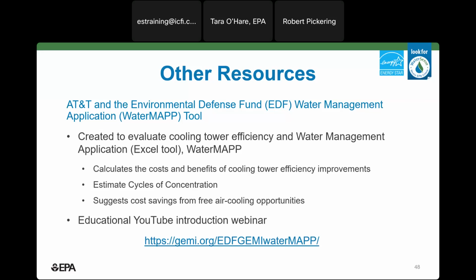We didn't talk much today about free air cooling, but this is a concept of using outside air that is at low temperatures to assist with cooling loads. Using free cooling can reduce your facility's energy and water use. And then finally, the cycles of concentration estimator takes information about your water quality and estimates the recommended maximum cycles of concentration for your cooling tower. So we talked a little bit about that earlier of how to calculate your target cycles. This is a tool that can help do that for you.